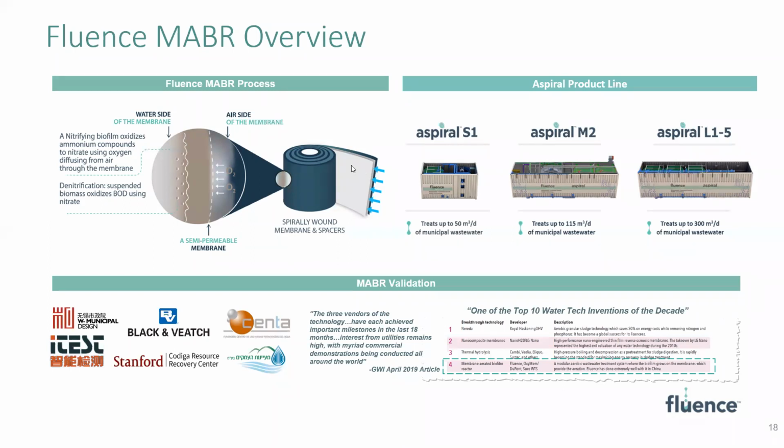The membrane is a self-respiring membrane that also supports a biofilm. The biofilm is aerated by the membrane and treats the wastewater. So the MABR is used to remove total nitrogen using very low aeration energy.